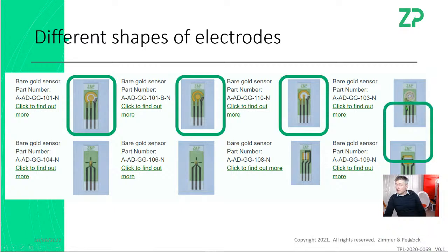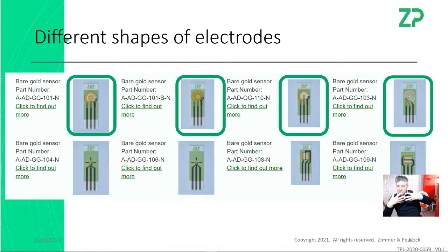Here we have a spiral. We did the spiral because some people are interested in measuring impedance. They think that interdigitated electrodes are a good idea. Interdigitated electrodes are really lines of electrodes that are very close to one another. And so we achieved the same as an interdigitated electrode, but in a spiral format. The quick answer is we found out that it doesn't matter what this geometry is. It really doesn't make a critical difference to a sensing application. You might have a slightly higher current density with some of these designs, but it's not the thing preventing you from a successful experiment.